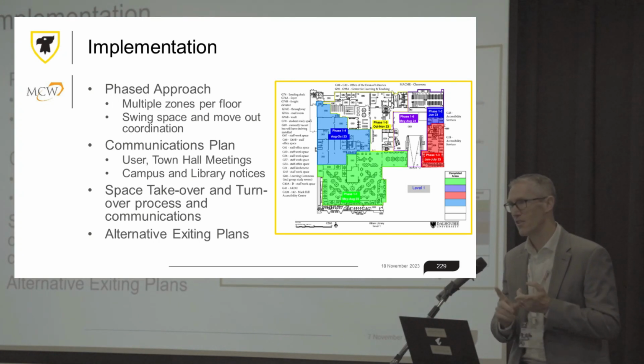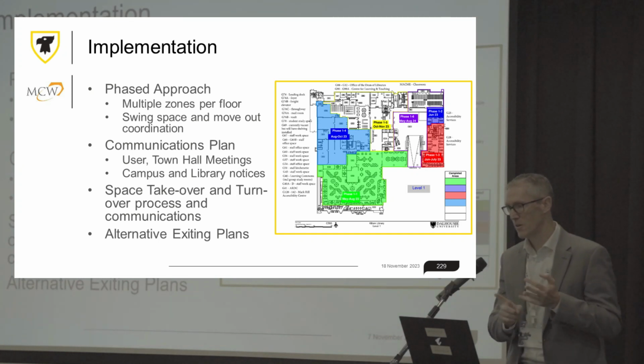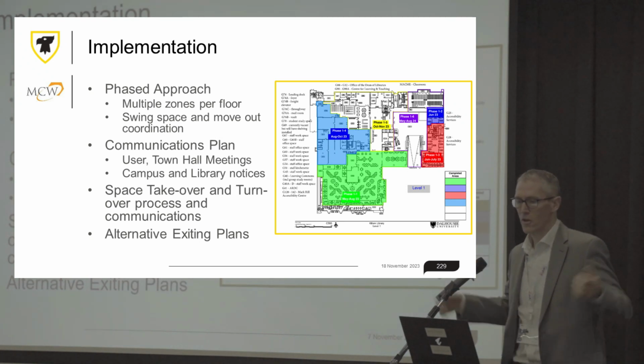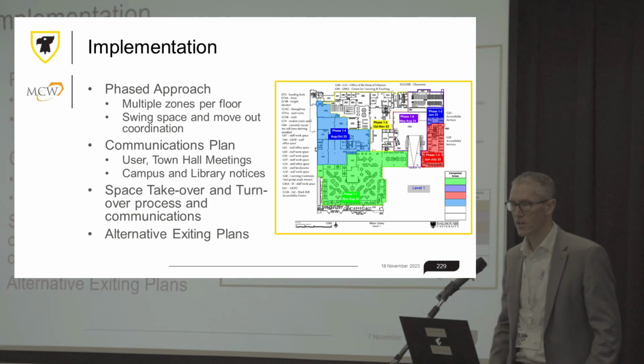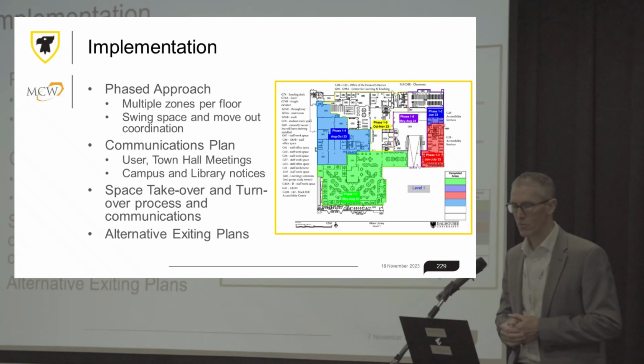And so people's complaints are, there's not enough outdoor light. It is dark in the building because it's older lighting. The ventilation is poor because you don't have good controls on all of the dual duct terminals. So invariably it's those, but every now and then you find a gem and you say, this room is always very, very cold. So you look at that and you say, can we do something and solve those problems? Those are the types of things that we've been working our way through.